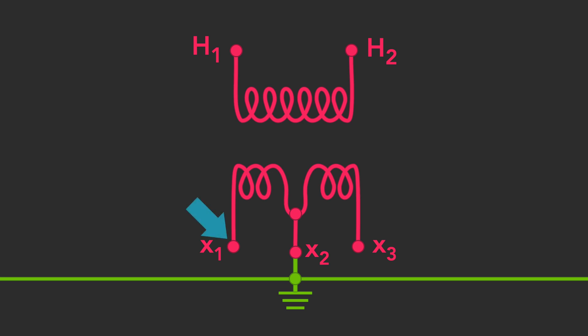Each winding connection, X1 to X2 and X3 to X2, provides 120 volts. A connection between X1 and X3 will yield 240 volts.